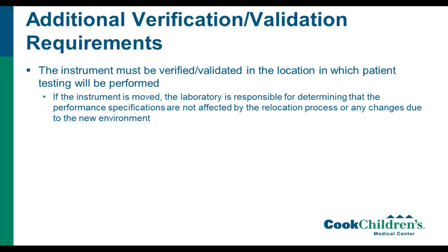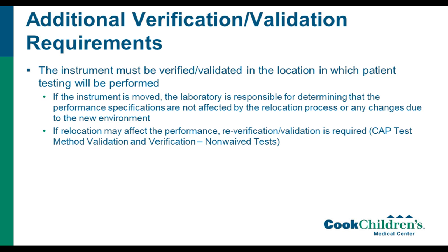And so CAP is a little bit gray on this, and they don't give definitions of, if it's moved over 25 feet to a new building. They don't specifically say, but the lab is responsible for determining if, when they move it, it may affect the performance of the assay.